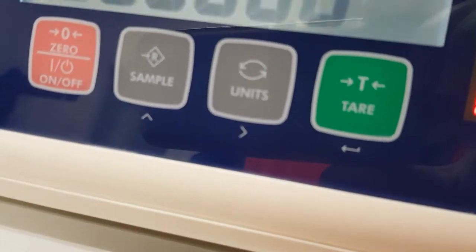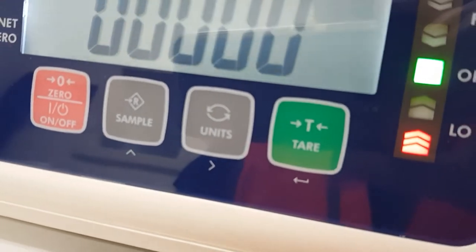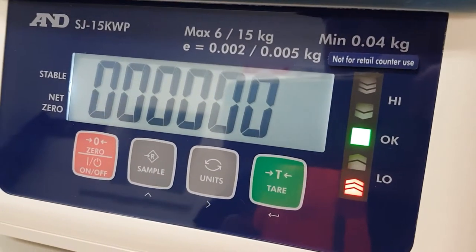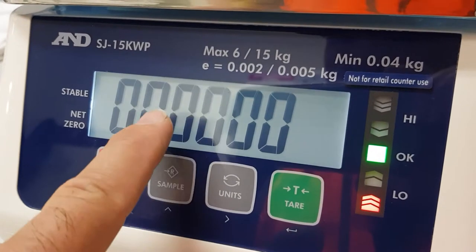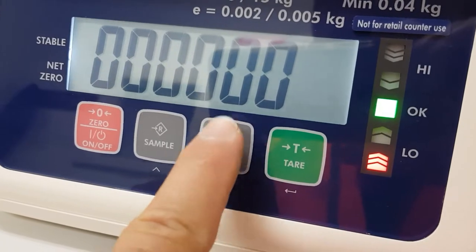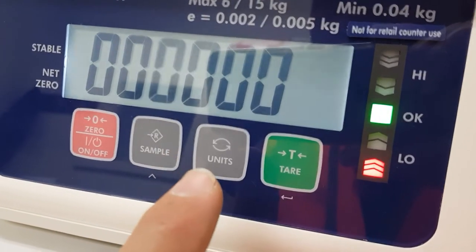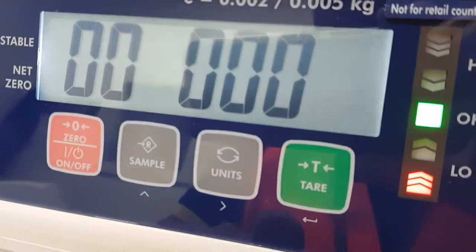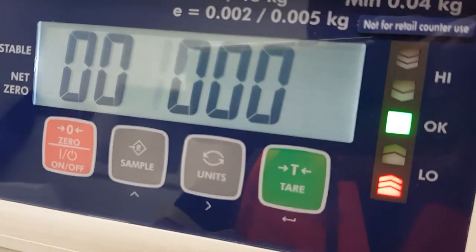We want the one thousands digit to start flashing. We press the right hand arrow, the units key, and then press it again until the one thousands digit is flashing. Then we increment it to the value you want, in this case one thousand. Then we can move on to the next set point.